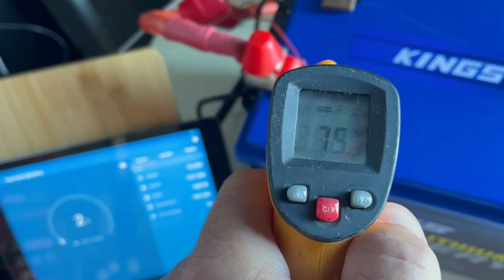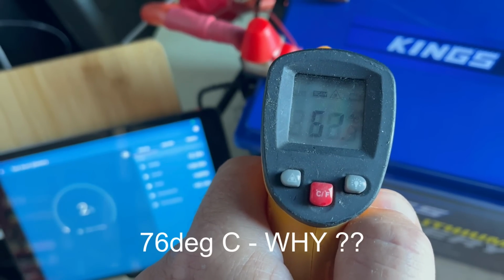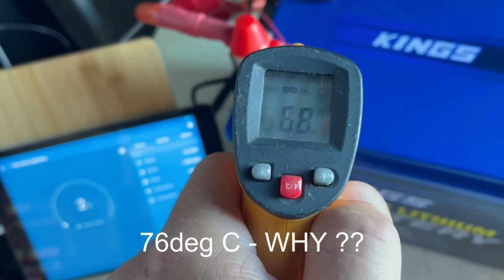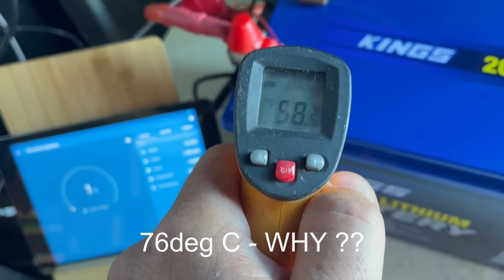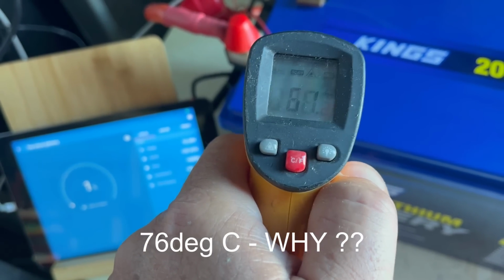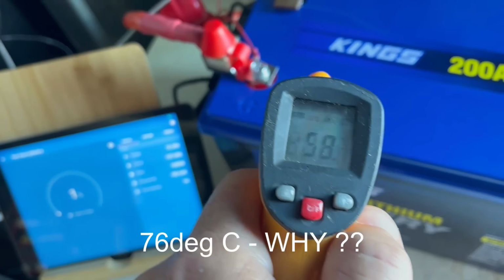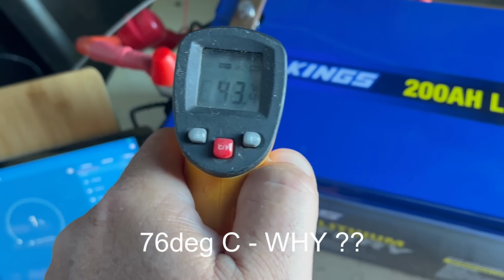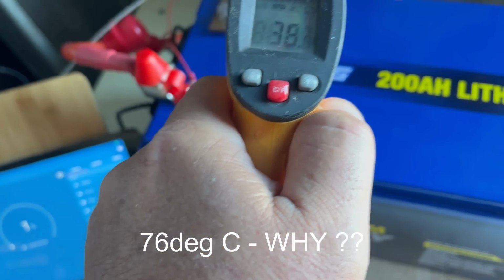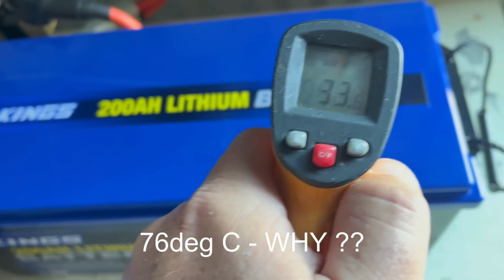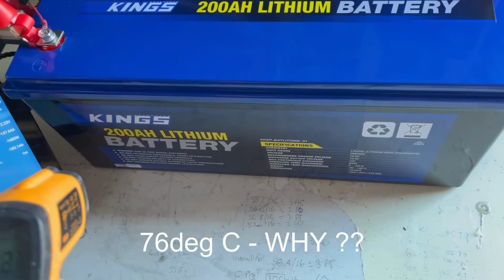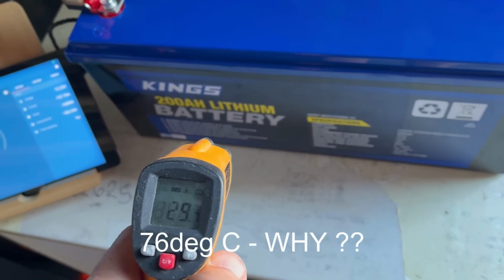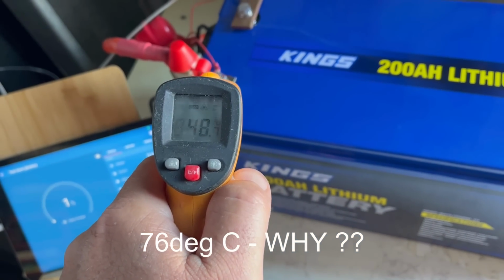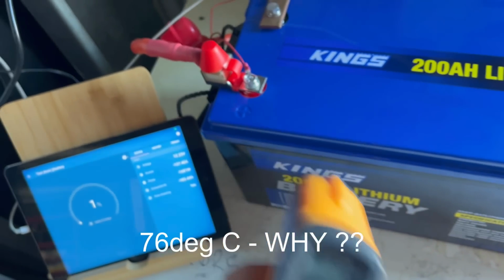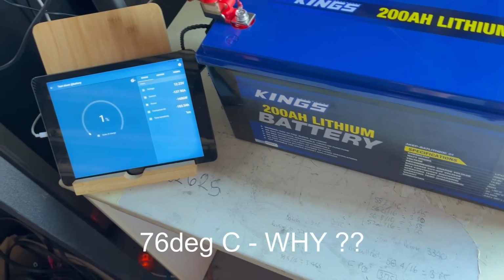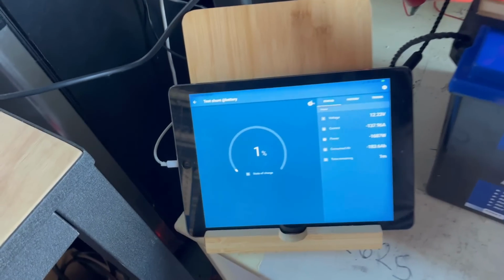So you can see the temperature there, 75 degrees - that's not ideal. And I did check those terminals, I double checked them, I've done them with a tension wrench, so there shouldn't be a problem. The rest of the battery's not hot anywhere. It'll be interesting to see the size of the cable underneath that positive battery terminal, so we'll know that when I crack the battery open. But we're going to stay with this.